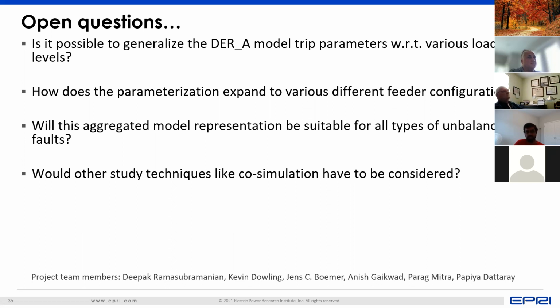It's usually designed to protect itself and not really coordinated. That's something where standardization can help, because a lot of times DER connected to the distribution system is off-the-shelf DER, which means you just buy the inverter off the shelf and whatever default settings are applied would usually be used. Now, there is an increase in distribution system level studies that look towards this kind of coordination, providing guidance on how the parameters of these DER can be set at the individual level to ensure that they don't fight with each other or cause oscillations with each other in terms of how they behave. I'm not sure if I answered all parts of that question, but if I didn't, feel free to send it to me by email and I can definitely answer it point by point.